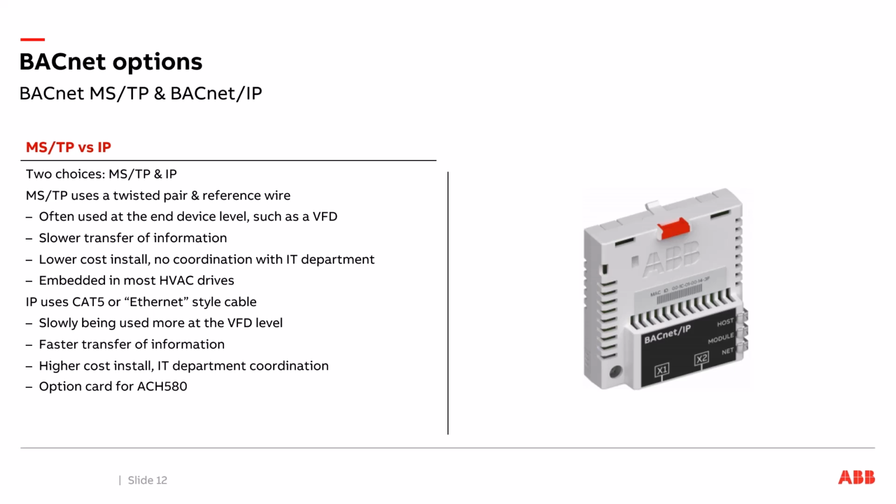If I wanted BACnet IP communications, you get that plugin card, snap it into the drive, and now it can talk BACnet IP. So we're slowly seeing more BACnet IP being used at the end device level like drives, but we're still mostly seeing MSTP. But IP is gaining popularity there. It's definitely a faster rate of transfer of information.